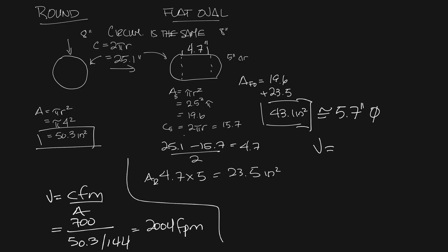Now on the oval, let's say we have that same 700 CFM. Velocity is going to equal 700 divided by 43.1, again divide that by 144, and that's going to come out to about 2339 feet per minute.